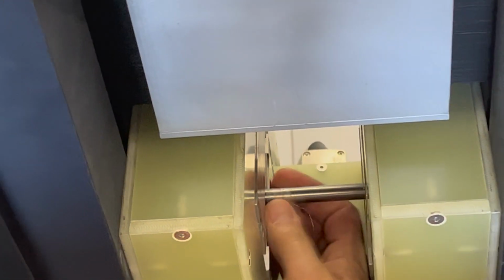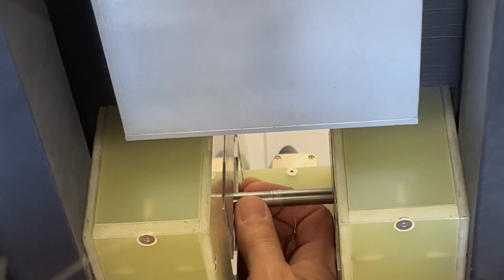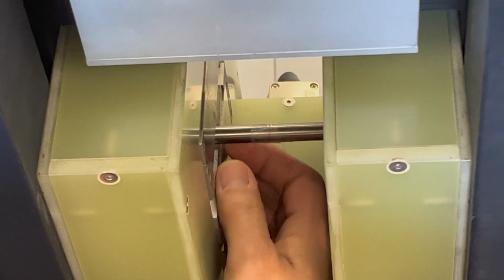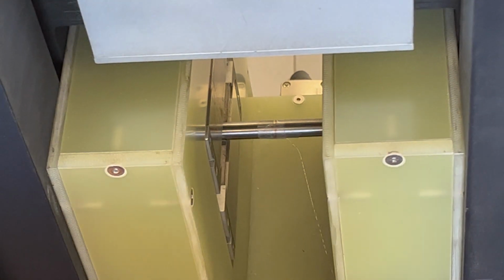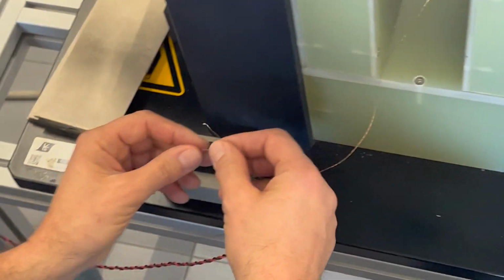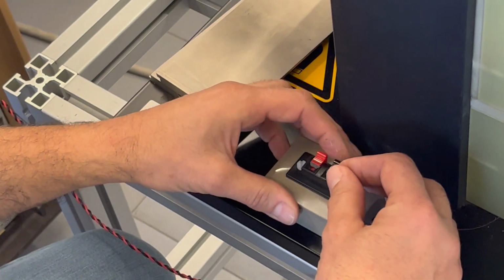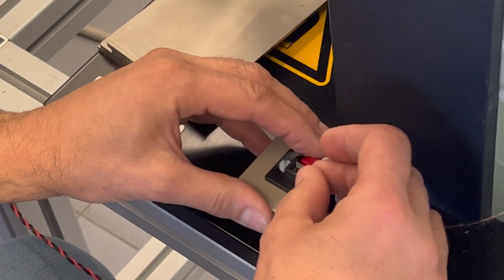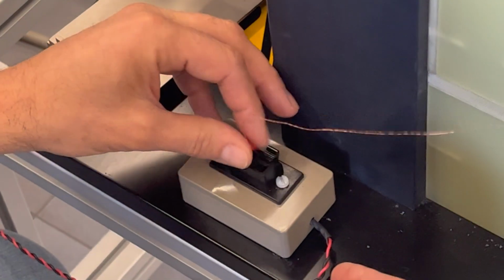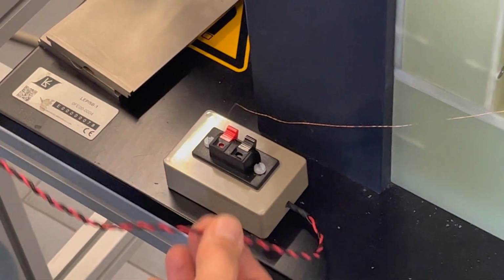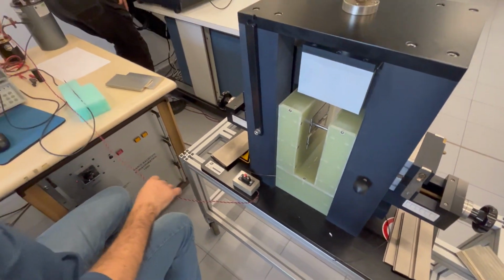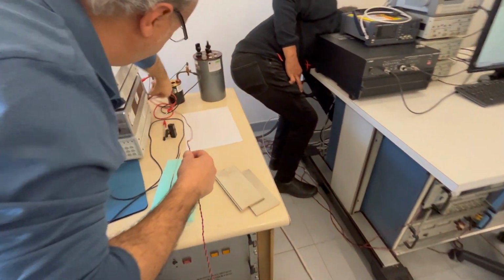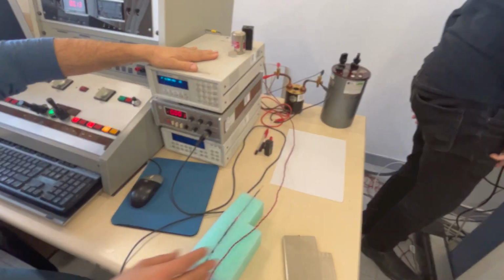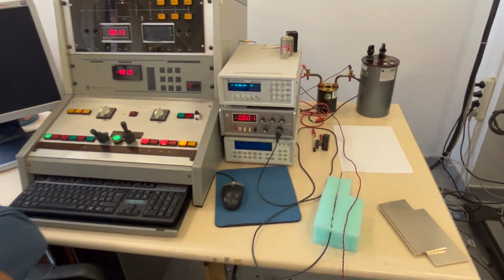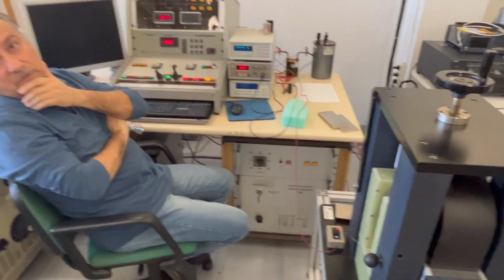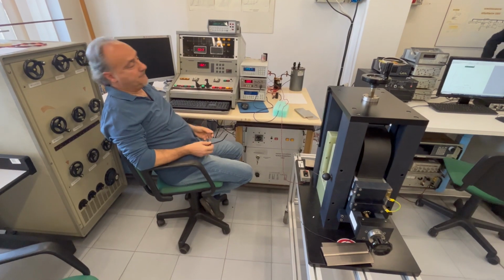The sample must be inserted with the pickup coil approximately in the center of the gap of the permeameter. The free ends of the wires of the pickup coil will be clamped into the permeameter. The polarity is not important. The signal measured by the pickup coil will go to the flux meter. The flux meter is periodically checked with a calibrated mutual inductance of known value.